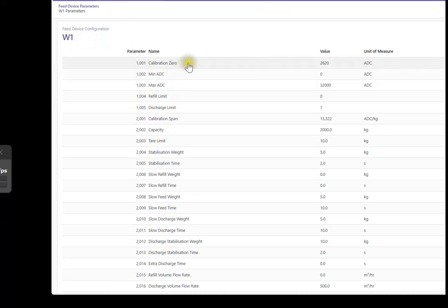So first of all, the weight comes in from the PLC, and when the weigher is at 0, the value from the PLC, what we call ADC values, that's analog to digital converter, so the value from the card comes in and it's 2620. Down here, the calibration span is 13.322, so that's ADC units per kilogram. So for every kilogram that the scale goes up by, it goes up by 13.322. Therefore, if the weigher had 2 kilos in, it would be this 2620 plus twice this.